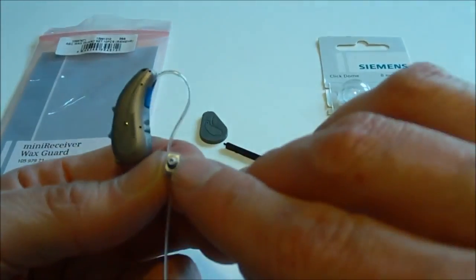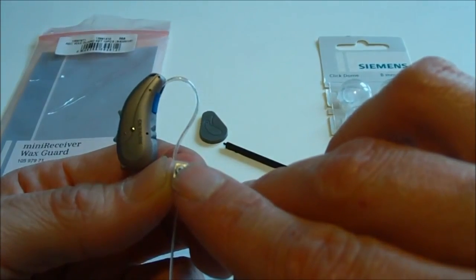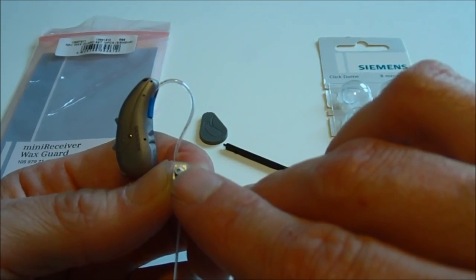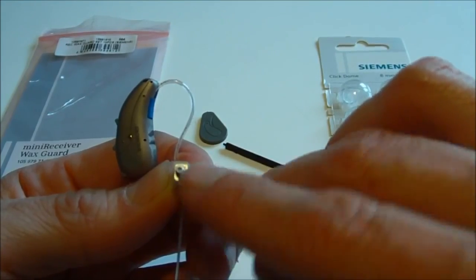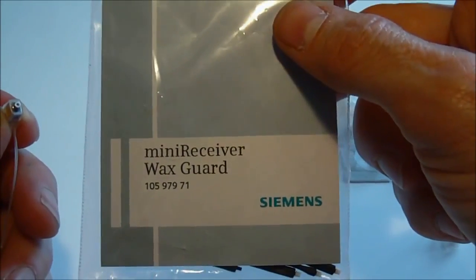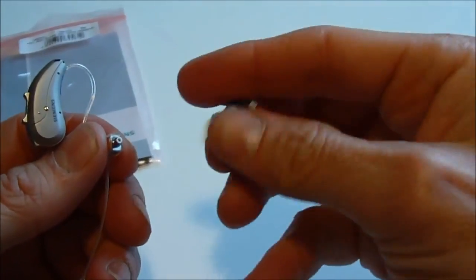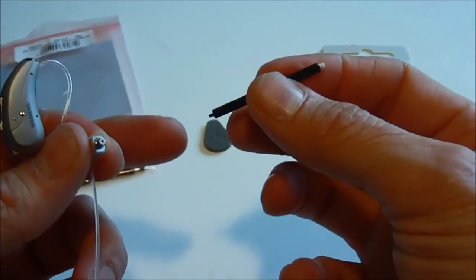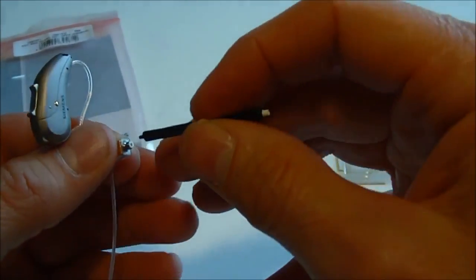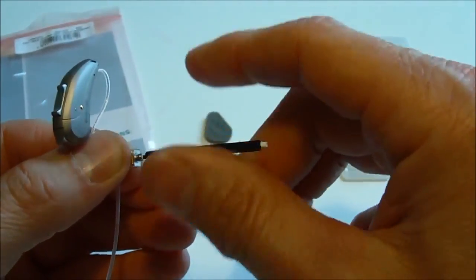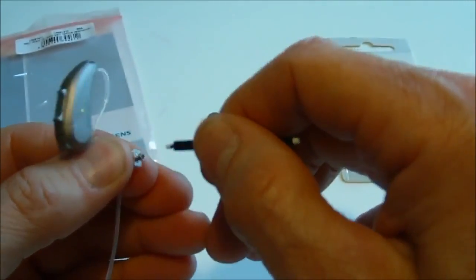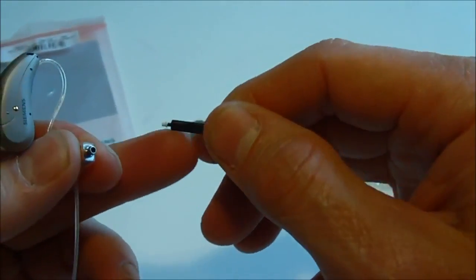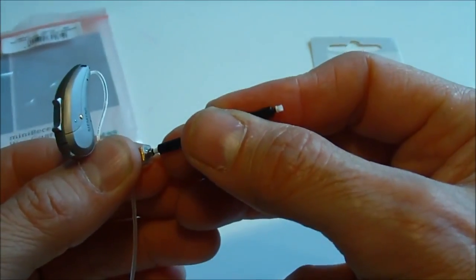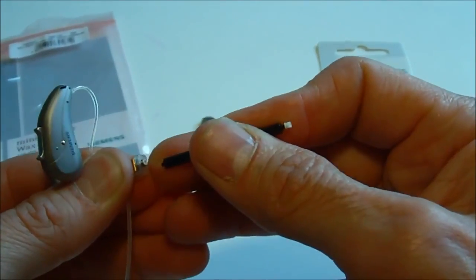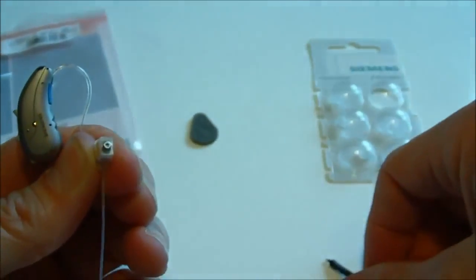If we look into the speaker, you'll see there's a white wax guard. On the Siemens Binax, these are called mini receiver wax guards, and on the pack you will see they say mini receiver wax guards, and they come in packs. And to change that, take a spare one. We'll see there's a new one on the end, and there's a screw tool to take the old one out. So you turn it clockwise into the wax guard and pull out, and you can see there it's on the end. Turn the stick around, push in and out, and then push on with your thumb.